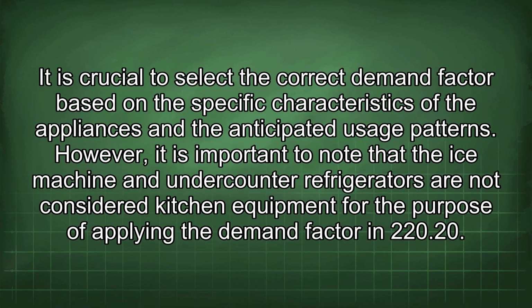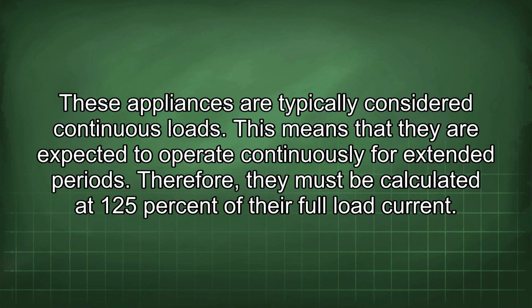It is crucial to select the correct demand factor based on the specific characteristics of the appliances and the anticipated usage patterns. However, it is important to note that the ice machine and under-counter refrigerators are not considered kitchen equipment for the purpose of applying the demand factor in 220.20. These appliances are typically considered continuous loads. This means that they are expected to operate continuously for extended periods. Therefore, they must be calculated at 125% of their full load current.